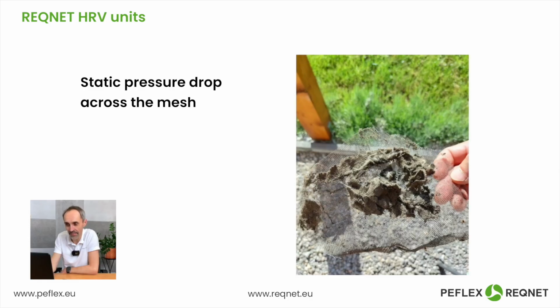Pressure drop across the mesh. When we discussed the intake and exhaust grills, we talked about the possibility of dirt and contaminants settling on the mesh. So here's another example of such a mesh, where all these contaminants accumulate and we get additional local resistance on that mesh. So the recommendation is, if you have a mesh with fine openings, just remove it from there.